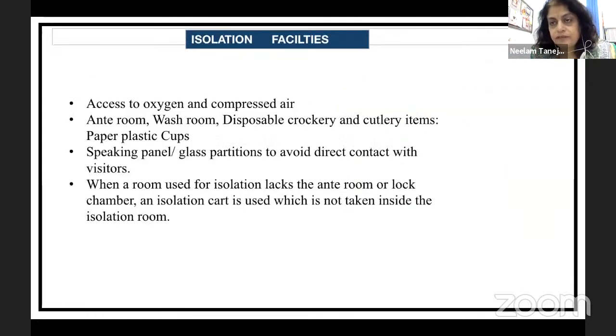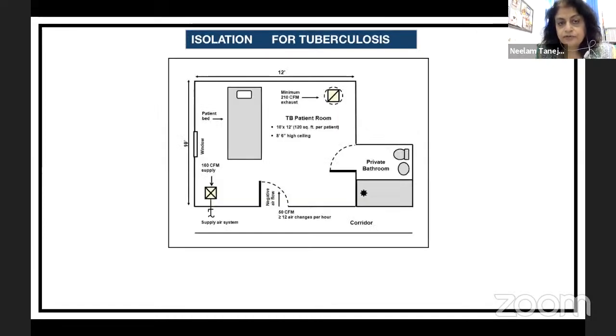Whatever isolation facility you design, negative pressure or positive pressure, it should have access to oxygen and compressed air. It should preferably have an ante room. There should be a washroom and disposable crockery, but a must is having a speaking panel or glass partition to avoid direct contact with visitors. And when a room lacks an ante room, you could use an isolation cart, which is not taken inside the isolation.